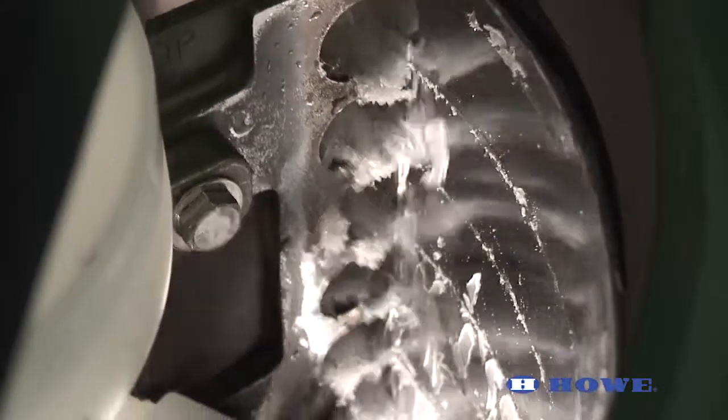After a few minutes have passed, look down into the evaporator freezing area. Ice should be freezing and harvesting over the entire evaporator from the top all the way down to the bottom on each rotation.